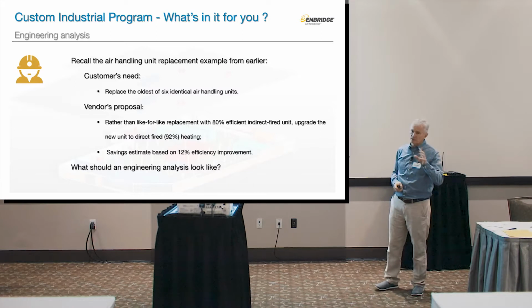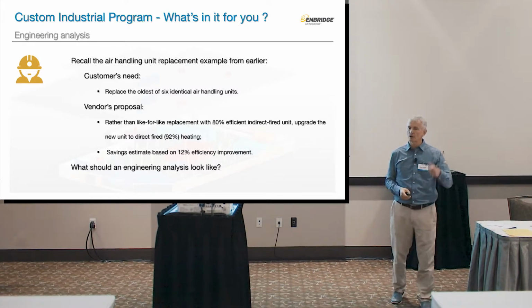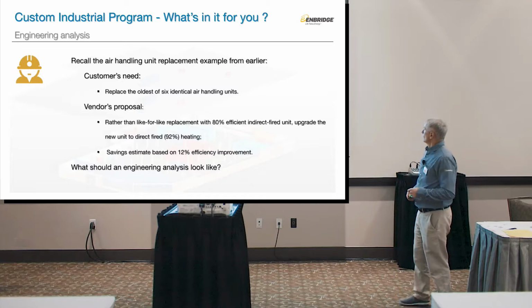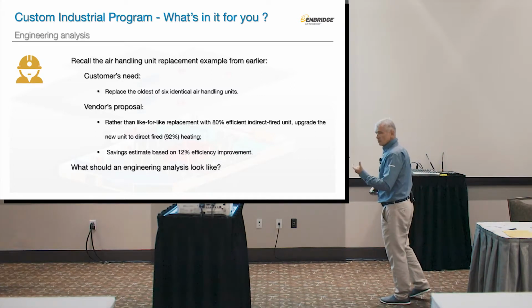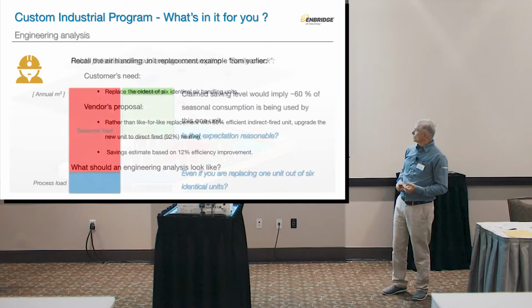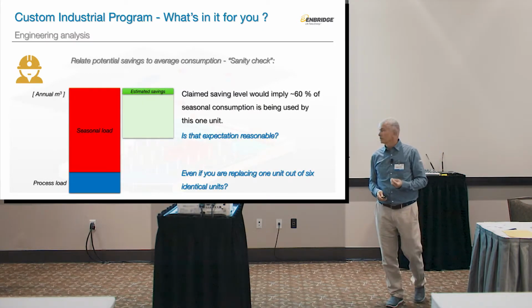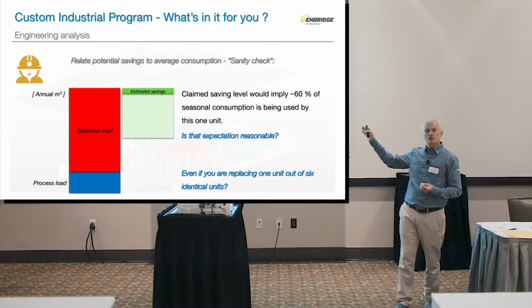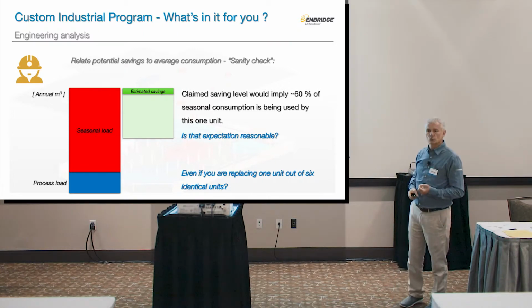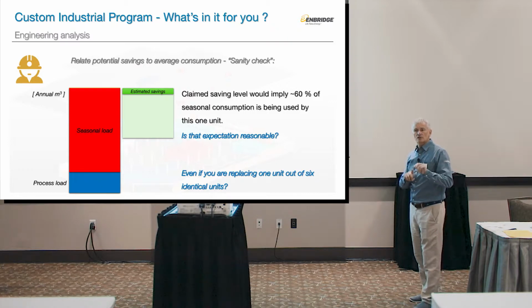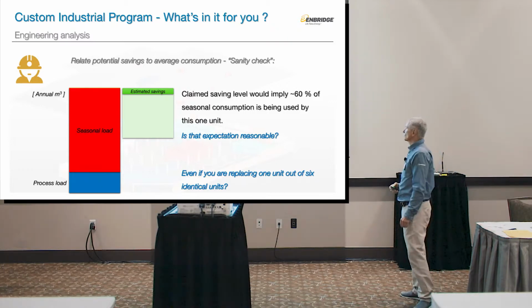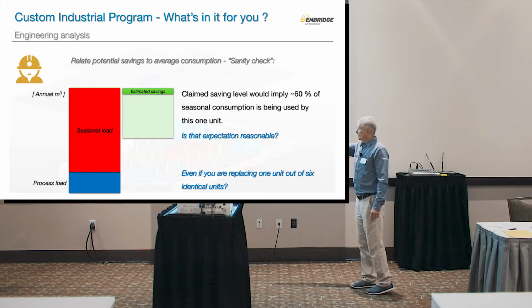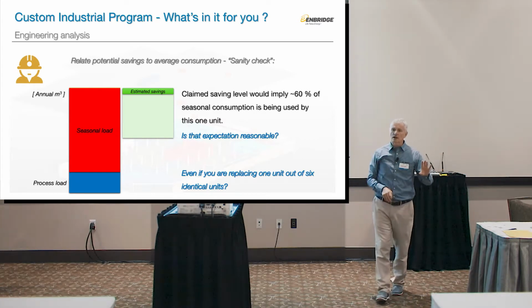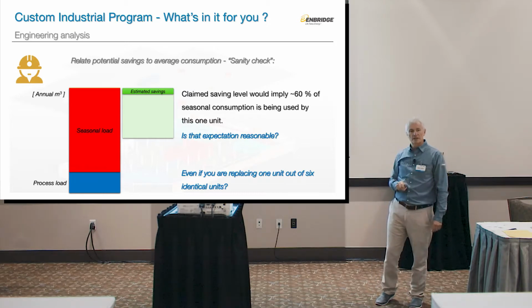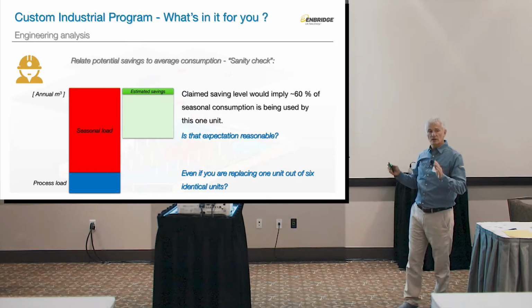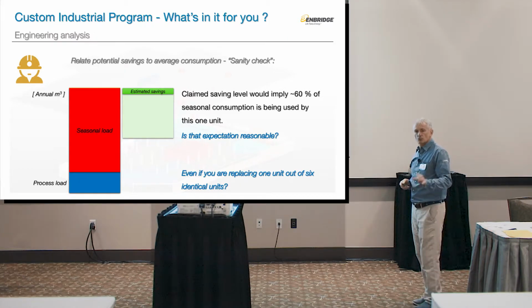So if you recall that example where they wanted to replace an air handling unit with a 12% more efficient one, what would engineering analysis look like? What would we do? What we have done, we turned it into a sanity check. We said, okay, this is your annual usage in this facility. This is the total natural gas that you use. Remember, they have 6 makeup air units, and they have some other equipment. So out of that consumption, the bottom is process load, so you cannot affect it with your air handling unit. Only seasonal load can be affected by your air handling unit. We agreed with the customer that this is a reasonable seasonal load. There is no process in there.